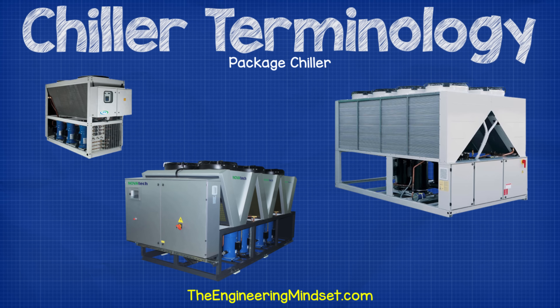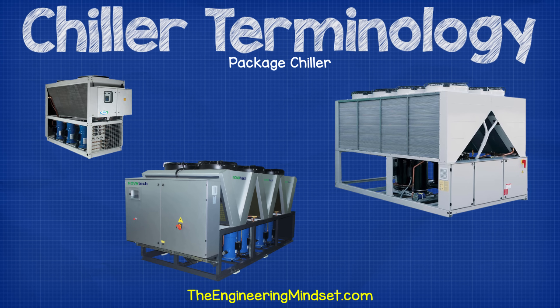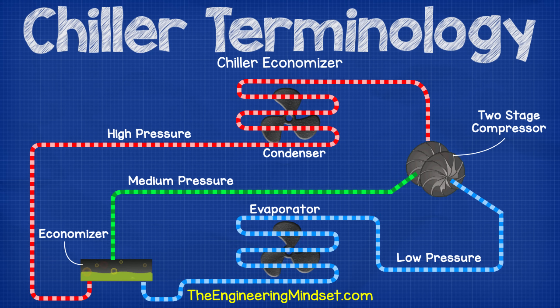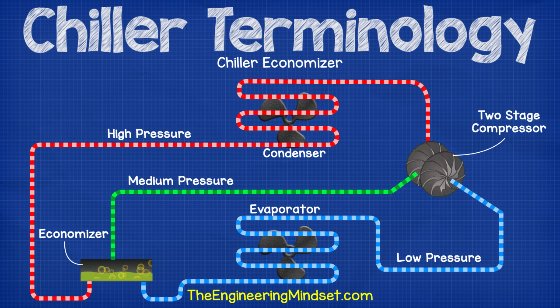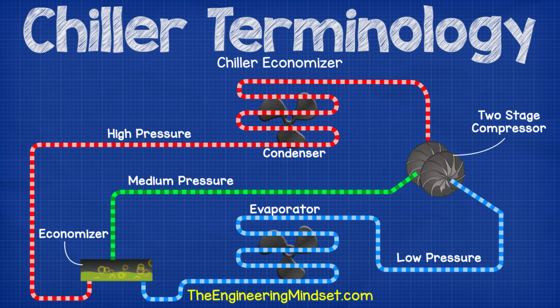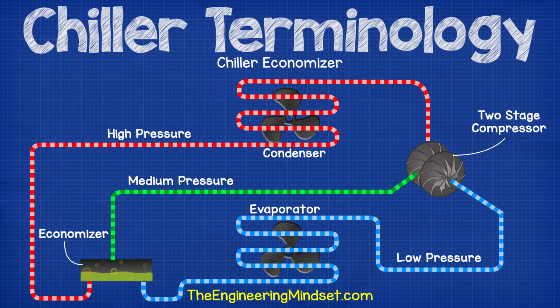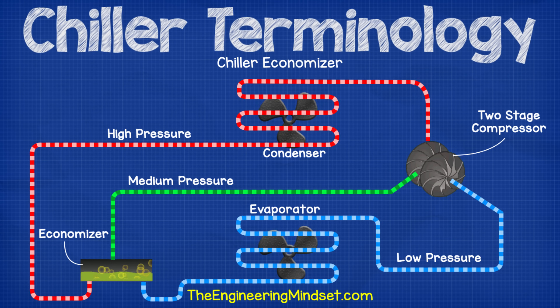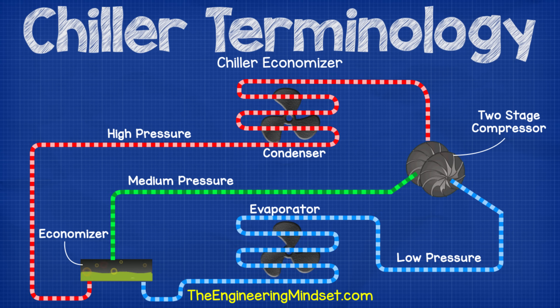Package chiller. This refers to a chiller which comes from the manufacturer in one complete bundle with all the major refrigeration cycle components in one package. This is the most common type of chiller and can include water or air-cooled designs. Chiller economiser. An economiser is used in some centrifugal type chillers with two-stage compressors to reduce energy consumption. A special tank is placed between the condenser and the evaporator — the refrigerant is partly throttled into the tank and any refrigerant which vaporises is sent straight to the second stage of the compressor. The rest of the liquid refrigerant continues to the evaporator, reducing the work required by the compressor and thus saving energy.